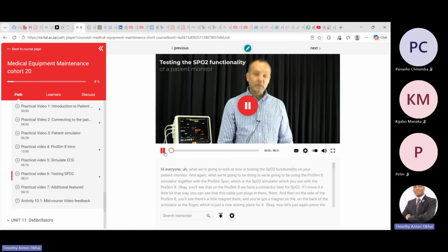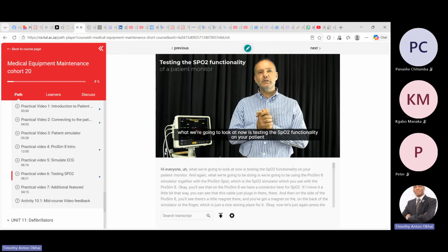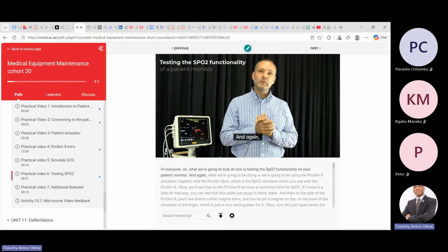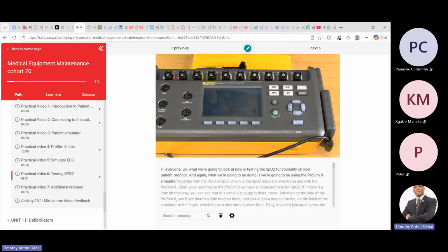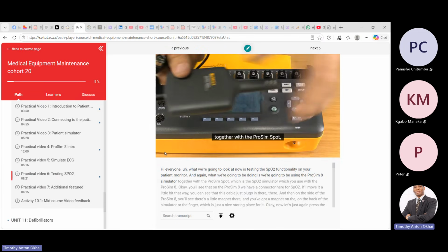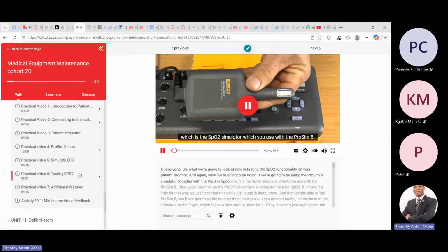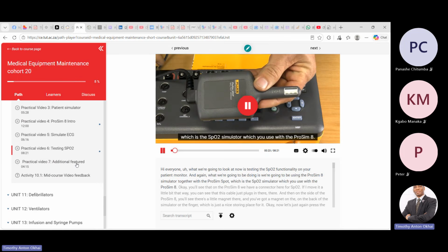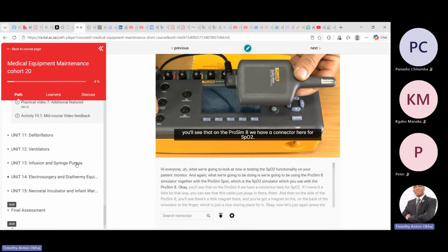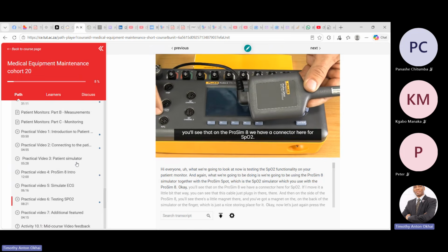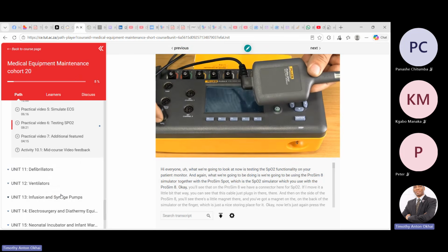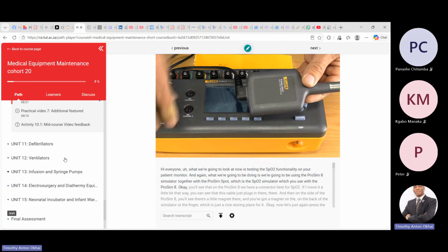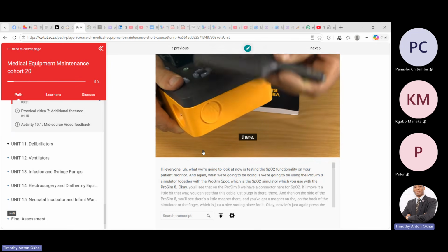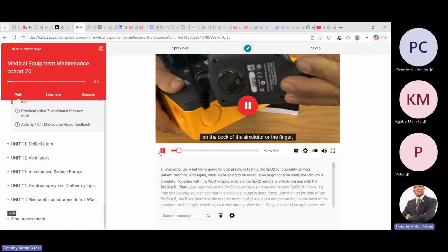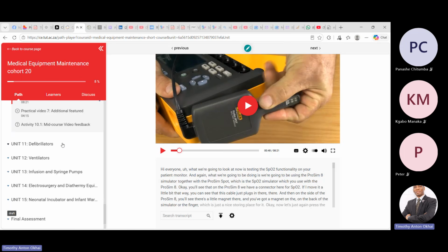Hi everyone. What we're going to look at now is testing the SpO2 functionality on your patient monitor. And again, we're going to be using the ProSim 8 simulator together with the ProSim Spot, which is the SpO2 simulator which you use with the ProSim 8. You'll see that on the ProSim 8 we have a connector here for SpO2. If I move it a little bit that way, you can see that. This cable just plugs in there. And then on the side of the ProSim 8, you'll see there's a little magnet there. And you've got a magnet on the back of the simulator or the finger.